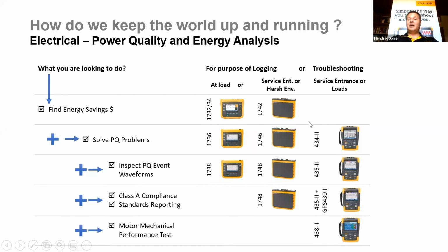This is more for power utility type customers where they want to log remotely via the built-in Wi-Fi hotspot functionality, or connect this via the fiber optic network or the actual copper-based substation network into a network where they can log in remotely. If you want to look at power quality problems, typically now we are looking at the 1736, 1746, and now we can also introduce, you guessed it, the Fluke 434, which is basically one of our workhorses that's been in the market for many years. If you want to inspect power quality event waveforms, the 1738 and then the 1748 and the 435-2 are the tools to use.